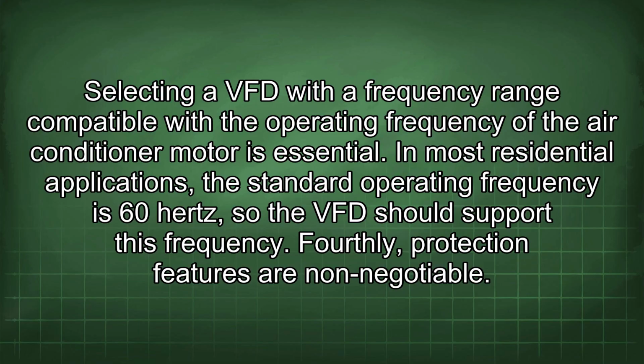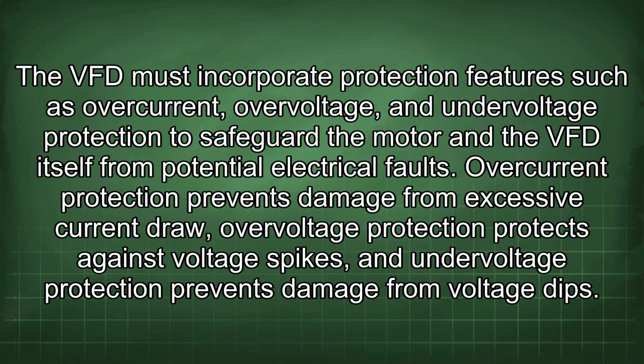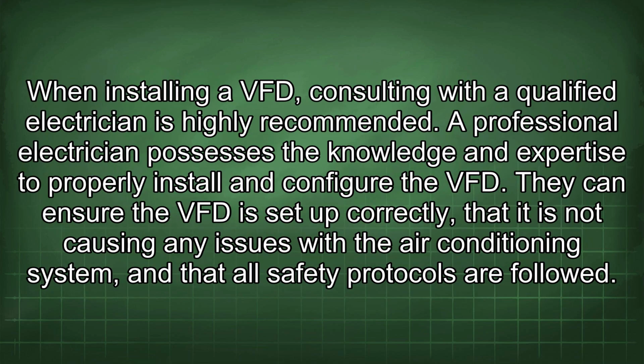Fourthly, protection features are non-negotiable. The VFD must incorporate protection features such as overcurrent, overvoltage, and undervoltage protection to safeguard the motor and the VFD itself from potential electrical faults. Overcurrent protection prevents damage from excessive current draw, overvoltage protection protects against voltage spikes, and undervoltage protection prevents damage from voltage dips. When installing a VFD, consulting with a qualified electrician is highly recommended.